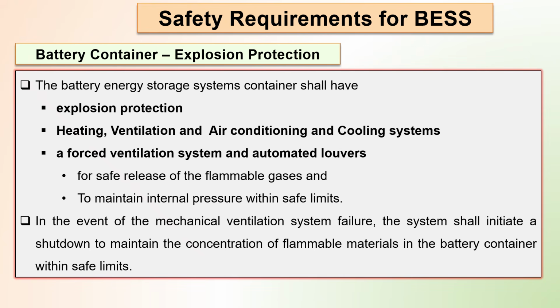After the definitions, the regulations give detailed provisions for different components of the battery energy storage systems, the safety requirements thereof. So first it gives provisions for battery container. The battery energy storage systems container shall have explosion protection as well as heating, ventilation, air conditioning and cooling systems. There shall also be a forced ventilation system and automated louvers for safe release of the flammable gases and also to maintain internal pressure within safe limits. In the event of mechanical ventilation failure, the system shall initiate a shutdown to maintain the concentration of flammable materials in the battery container within safe limits.